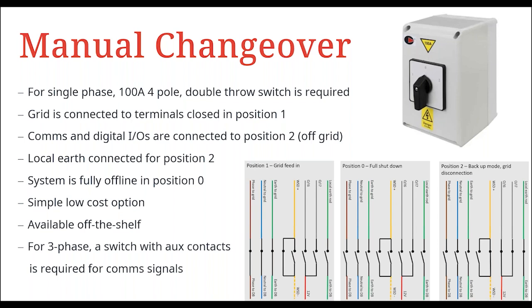So this is a really simple solution. It's low cost for these components. One thing to bear in mind is the smart meter needs to be on the grid side, and if the grid fails, the smart meter dies. We have the loss of voltage on the grid side, and we also have those digital signals. So we have actually 4 checks to make sure that we're in the correct mode. So it's a very robust, safe solution.